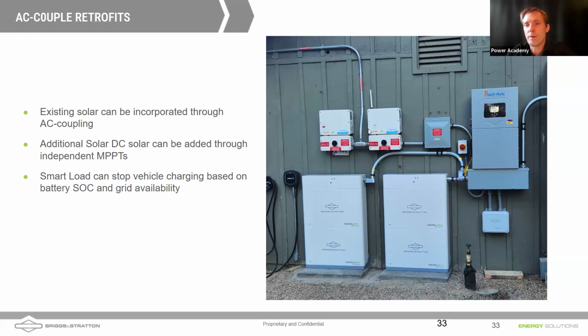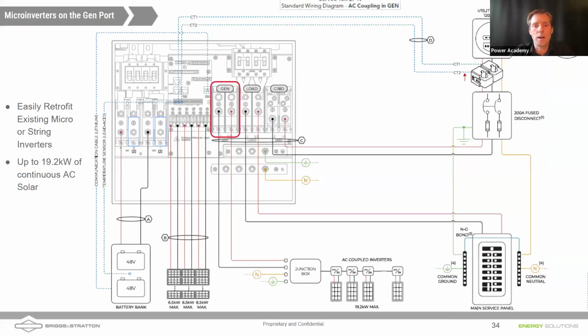The original system. But as long as we've integrated the Sol-Ark inverter with the batteries, the Sol-Ark inverter can be grid forming, and it can, from the battery power, cover the loads. It can also keep this AC coupled solar alive. So AC coupled solar, with a grid tied system, doesn't normally provide backup, but we can allow it to provide backup with a grid forming inverter like the Sol-Ark 15K.